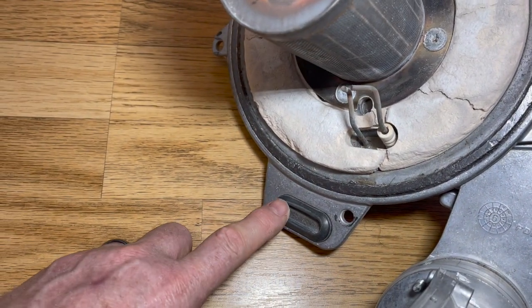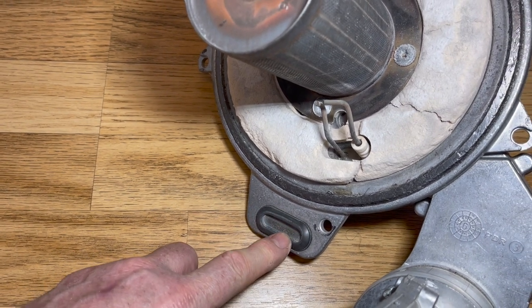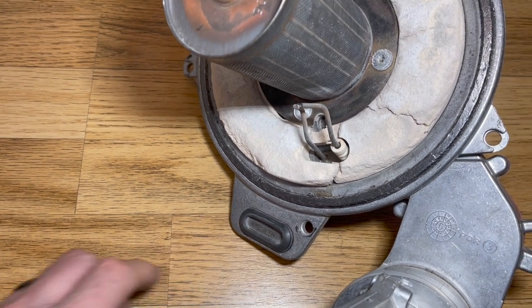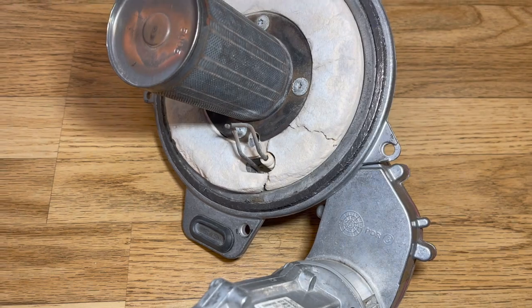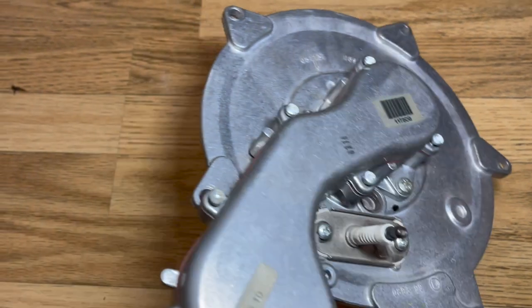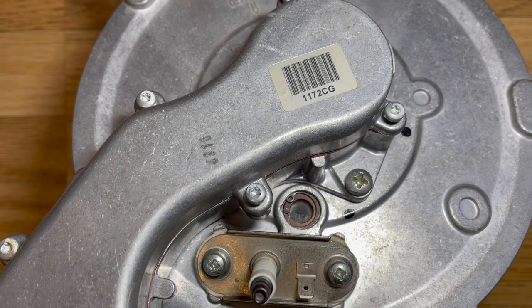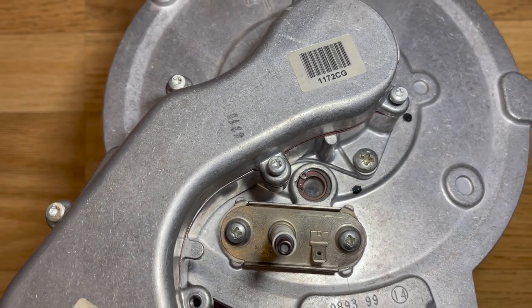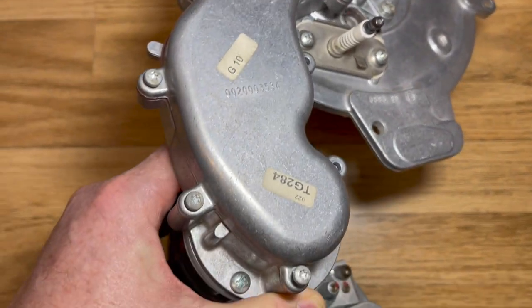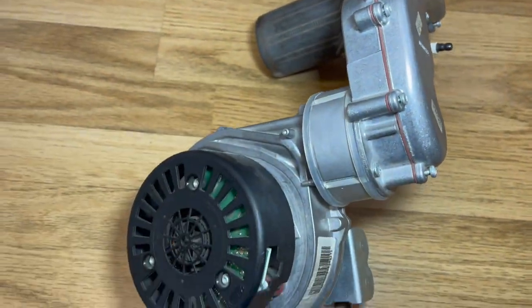Down at the bottom, the gasket needs to be replaced every time the door is removed — this is the seal for the bottom of the heat exchanger at the condensate point. Flipping the heat engine over, you can see where the HT lead connects. There's a little window in this boiler — most modern boilers don't have it as it slightly reduces efficiency. This is the blending tube where gas and air are mixed before going to the burner.